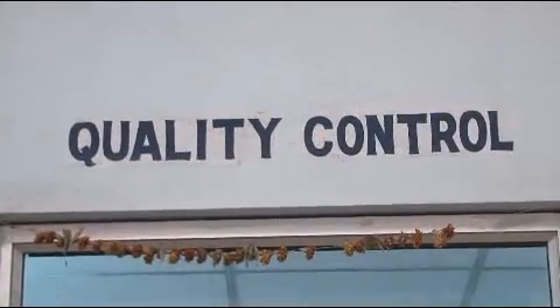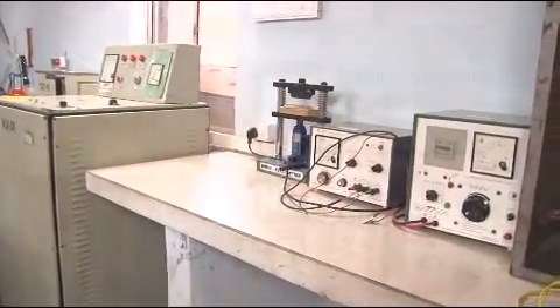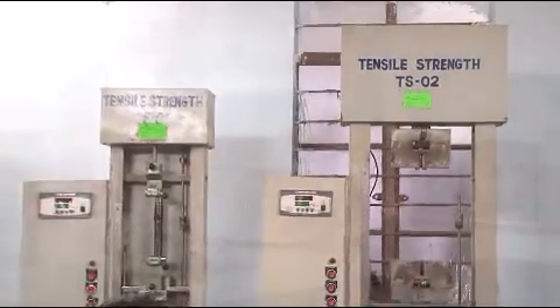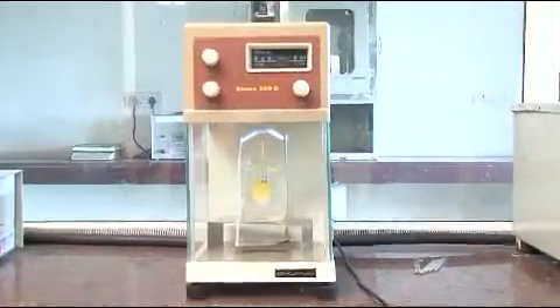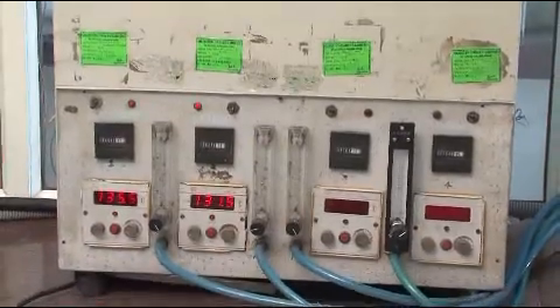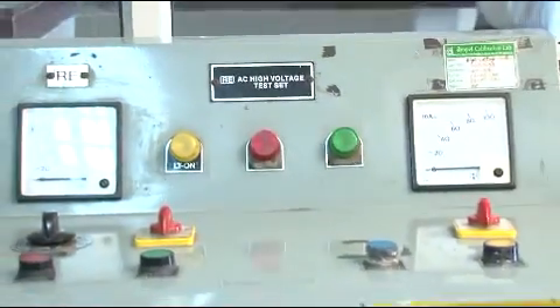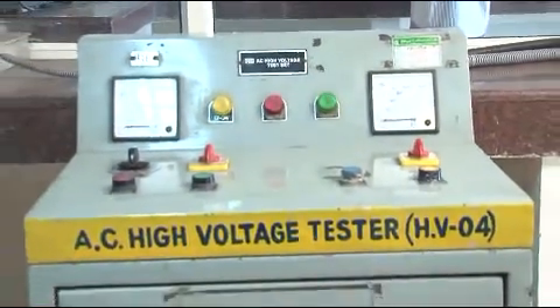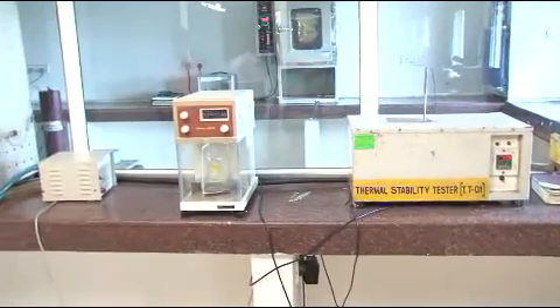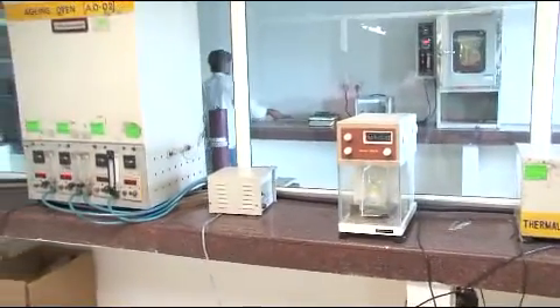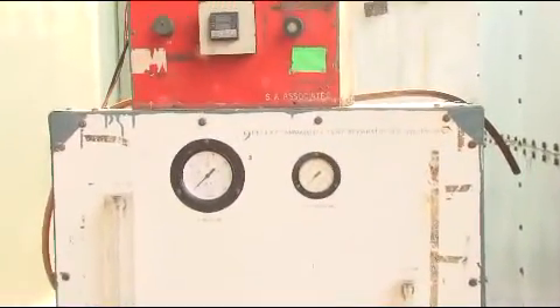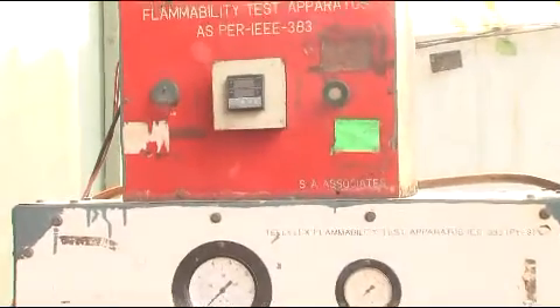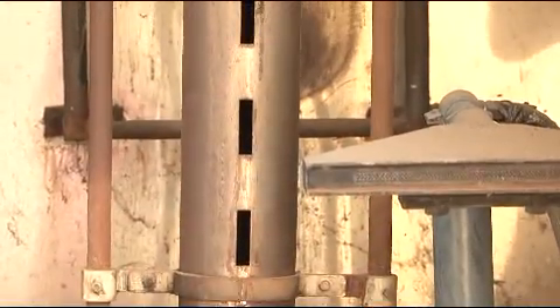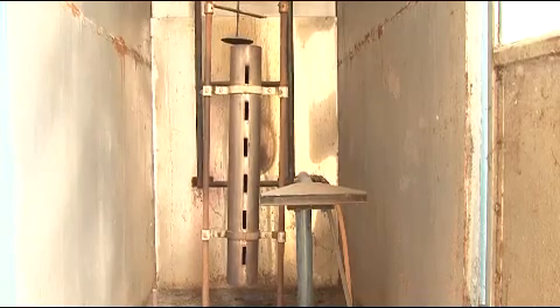In order to ensure quality, low voltage cables will have to pass through a series of tests, namely routine tests, type tests and acceptance tests. Conductor resistance test and high voltage tests are known as routine tests. Type tests are carried out on samples drawn from every production lot to check whether all parameters are in conformity with IS specifications. Acceptance tests are conducted in the presence of the external inspecting authorities to get their approval.